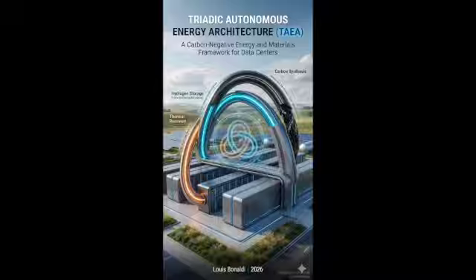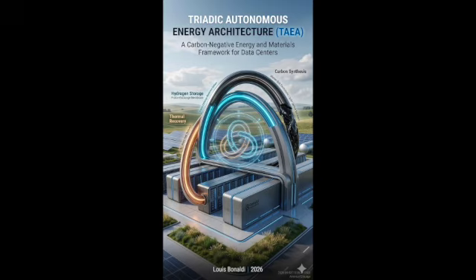If we look at the raw power distribution among these systems, the paper models System 1 pulling in about 10 to 12 megawatts of recovered power. But I want to understand how it's doing that, because data center exhaust isn't exactly a roaring furnace. Right, it's warm air. System 1 primarily relies on an organic Rankine cycle, or ORC, which generates about 9 to 10 megawatts. Unlike a traditional steam turbine in a coal plant that boils water at extreme temperatures, an ORC uses an organic fluid, often a specialized refrigerant.